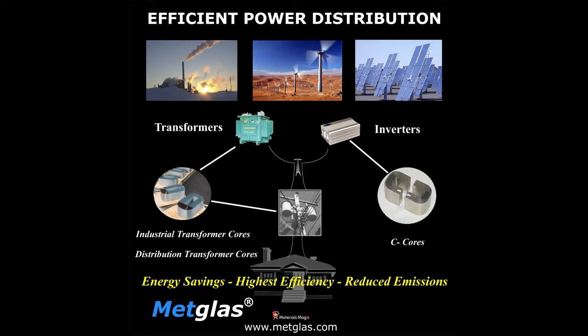The other element that causes the energy efficiency is that it's very thin, about thousandths of an inch thick. We compete against traditional silicon steels, cold-rolled, grain-oriented electrical steels. Those are at least 7 times thicker, sometimes 10 times thicker, than what we make, because we cast it in a one-step process, whereas they start with a slab of material and roll it down to a thin material, and it gets very expensive for them to go much thinner than they are today.